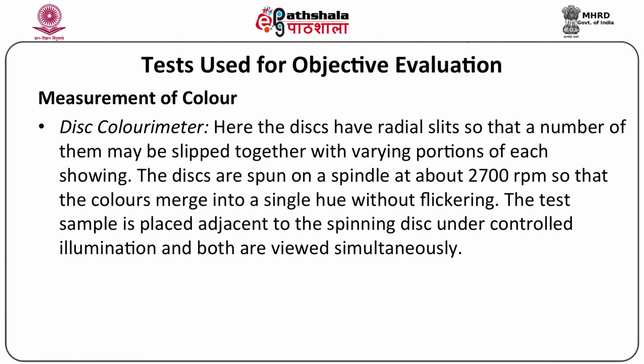Disc colorimeter. Here the discs have radial slits so that a number of them may be slipped together with varying proportions of each showing. The discs are spun on a spindle at about 2700 rpm so that the colors merge without flickering. The test sample is placed adjacent to the spinning disc under controlled illumination and both are seen simultaneously.